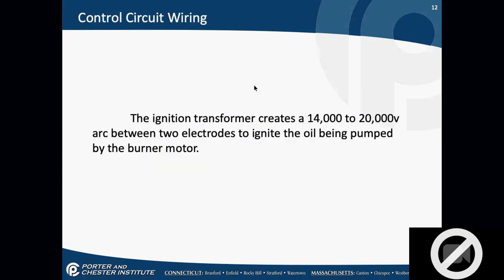The ignition transformer creates 14,000 to 20,000 volts between the two electrodes to ignite the oil being pumped in. The ignition transformer is a step-up or step-down transformer? Step up. It's a step-up transformer.